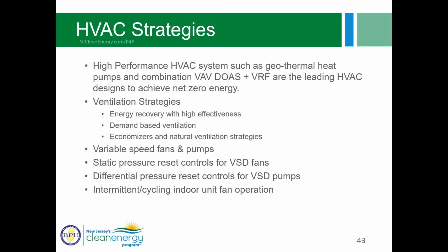So here's just an overview of some strategies to help with incorporating efficient elements and thinking of things to compare. So what do we want to compare? So here are just some points. In general, high performance HVAC systems, let me back up here. When we look at high performance buildings, which we will do in a little bit, and we look at, okay, what do they include? What kind of strategies? We tend to see geothermal heat pumps and a combination of, like we just looked at, the VAV, direct outside air units, and VRF. So we tend to see those kind of systems in high performing buildings. And typically those are employed to achieve net zero, because like I said before, those heat pump systems will help you really get your site EUI down.